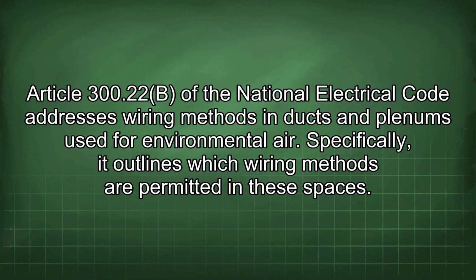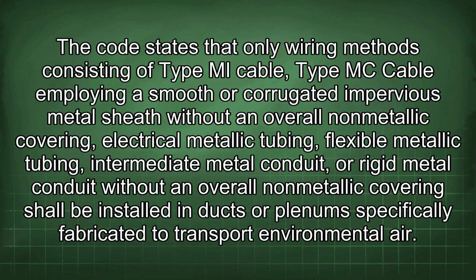Article 300.22(B) of the National Electrical Code addresses wiring methods in ducts and plenums used for environmental air. Specifically, it outlines which wiring methods are permitted in these spaces. The code states that only wiring methods consisting of type MI cable, type MC cable employing a smooth or corrugated impervious metal sheath without an overall non-metallic covering, electrical metallic tubing, flexible metallic tubing, intermediate metal conduit, or rigid metal conduit without an overall non-metallic covering shall be installed in ducts or plenums specifically fabricated to transport environmental air.